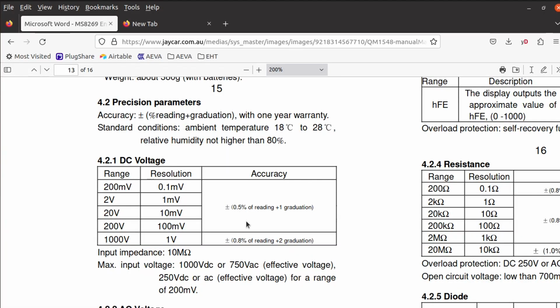But the accuracy is what we're interested in here. The way it expresses it is 0.5% of the reading plus 1 graduation. Now, 0.5% of the reading - 4 volts, let's divide it by 100 to give 1%, that's 0.04. Divide that by 2 to give 0.5%, that's 0.02 volts.